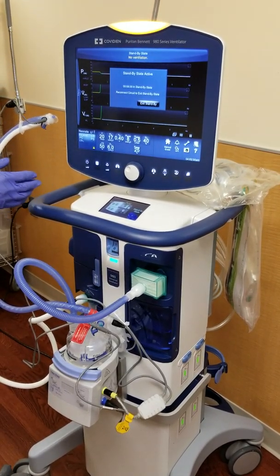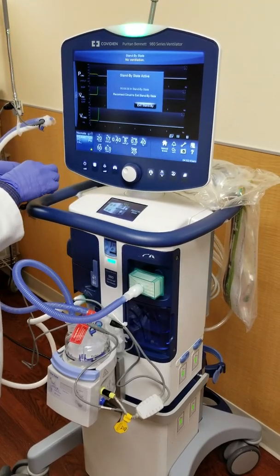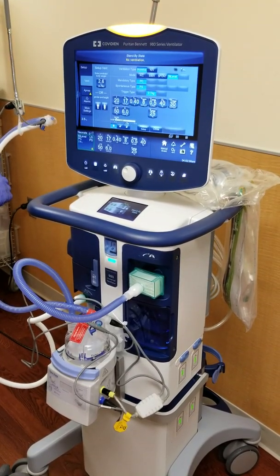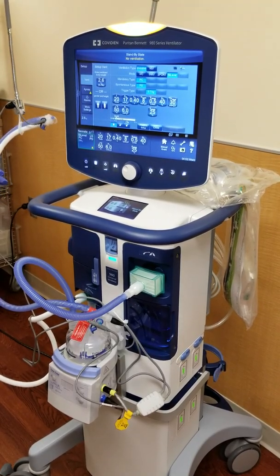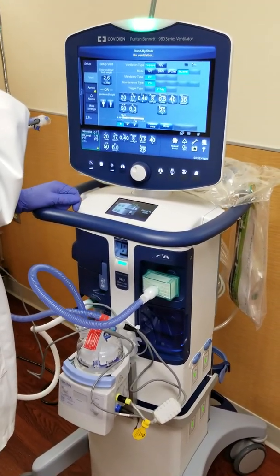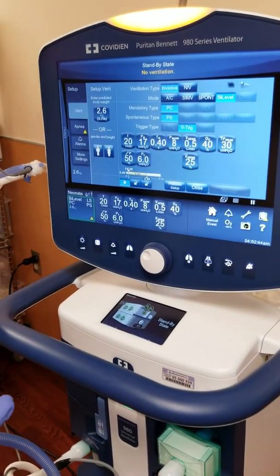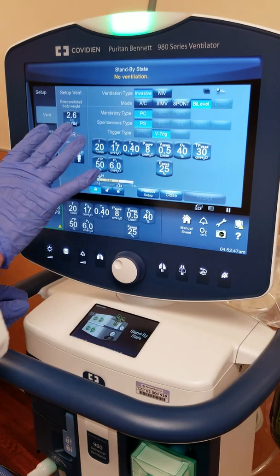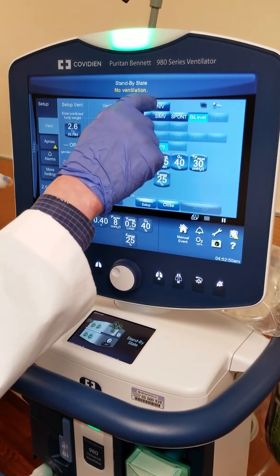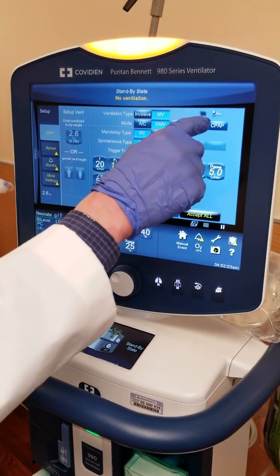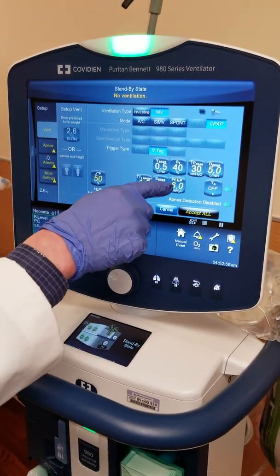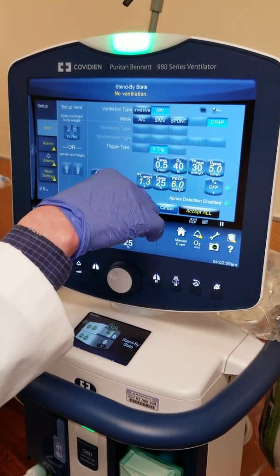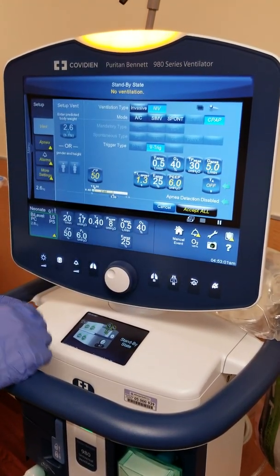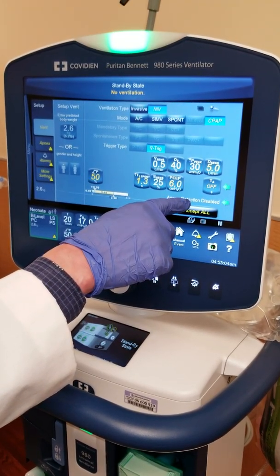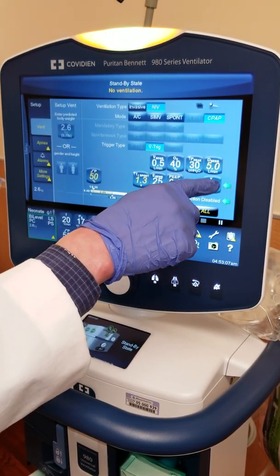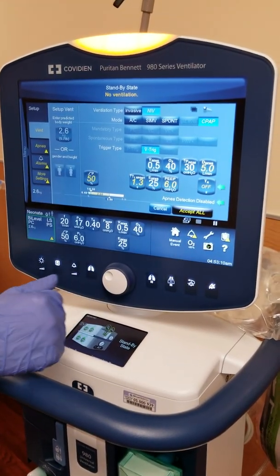So, as far as going here, I have it in standby. What I want to do is show you a couple different options. First off, what we would do if we just wanted to use this to provide nasal CPAP, what you're going to want to do in your mode options is go to non-invasive CPAP. And then you got your PEEP. Sensitivity, let it default. FiO2. You got a backup. You can set the apnea parameters. It's telling you to do that. It's telling you it's off, so you want to turn that on.